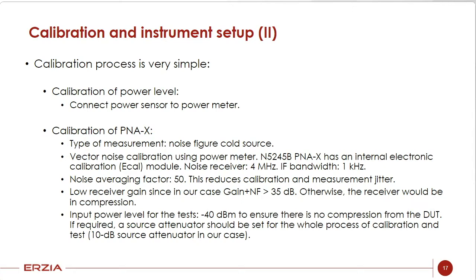In our case, the PNA-X has an internal electronic calibration module, so we don't need an external one. The noise receiver has been set to 4 MHz and the IF bandwidth to 1 kHz. The noise averaging factor has been set to 50 to reduce the calibration and measurement jitter. Regarding the receiver gain, we have set it to lowest state, since in our case, gain plus noise figure is above 35 dB. Otherwise, the receiver would be compressive. It means that, for example, if we are testing it in high state, our noise figure will be smaller, but it won't be true. So we have to be very careful of avoiding compressions from the equipment.